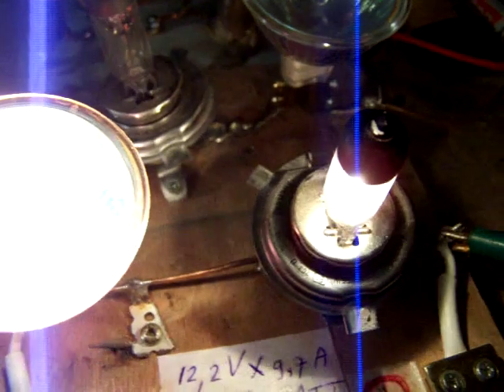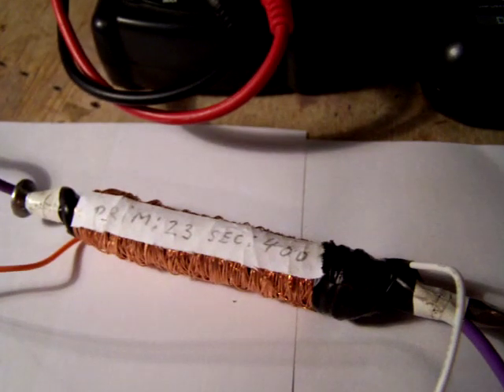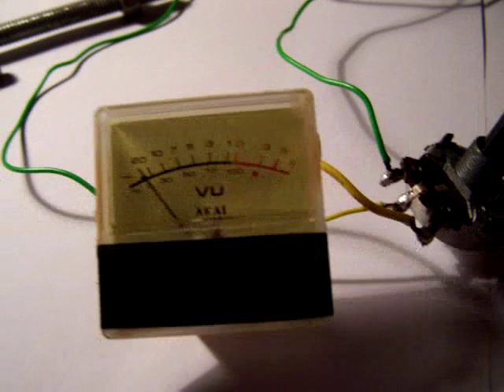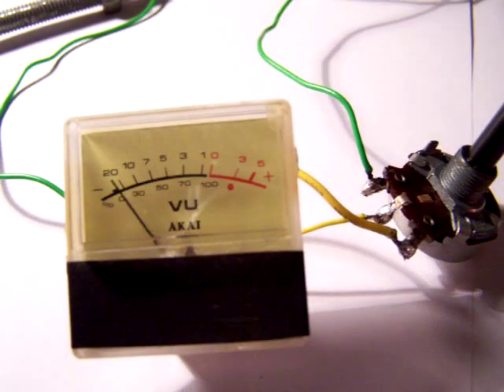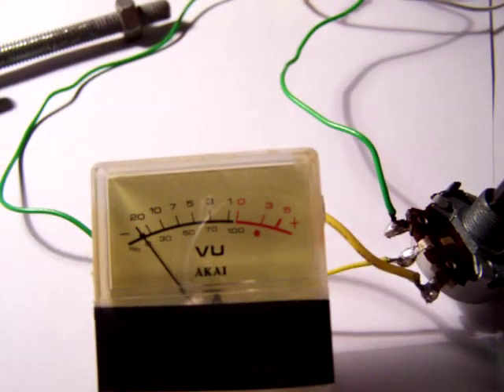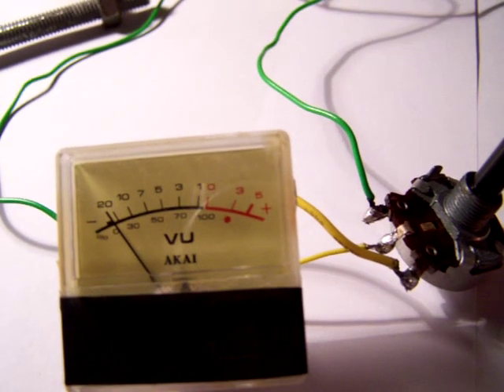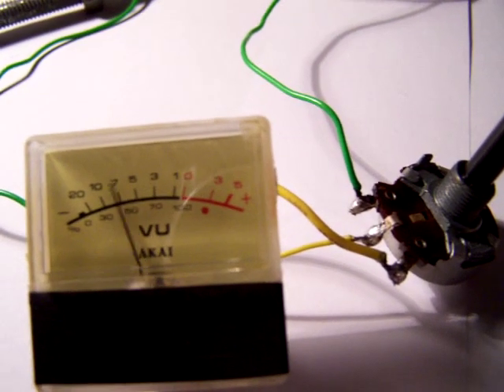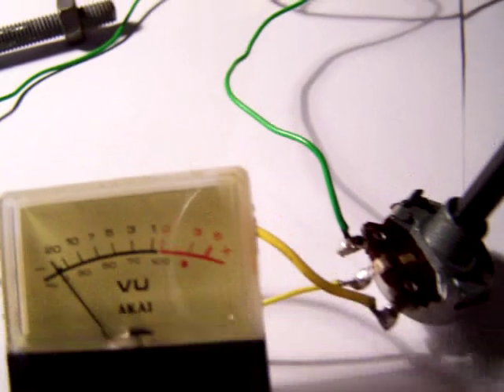As a load, I use this bank of lamps. Here you see quite a few heavy halogen lamps and car lamps. They are 50 watts. So it's quite a big load, and quite a big current flows here through the primary. And here you see that the meter moves. You can also see the inrush current, also important to know for certain circuits. You can see a peak of current.